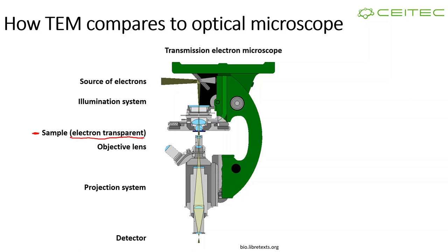The sample must be electron transparent — a very important requirement for transmission electron microscopy, not scanning electron microscopy. Electron-transparent matter starts from around 500 nanometers, and more likely 200 nanometer thickness is the practical limit for electrons. The thinner your sample, the better, because electrons interact strongly with matter — they like to interact with biological stuff and they will also damage it. You can illuminate a sample with photons for a very long time without damage, but electrons will essentially burn your sample.